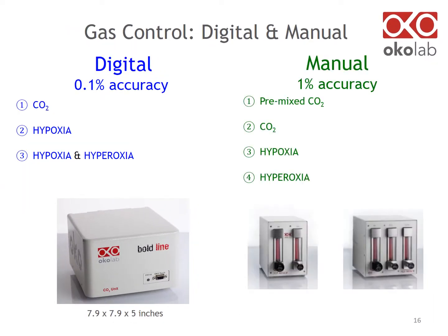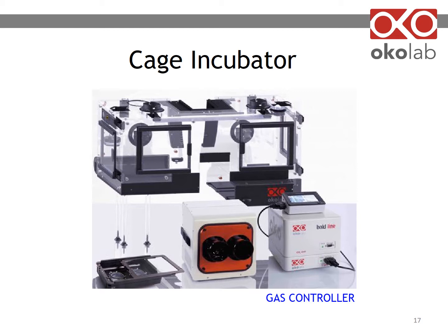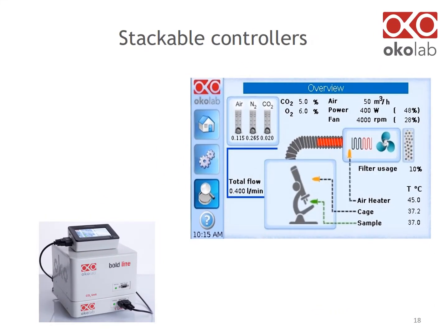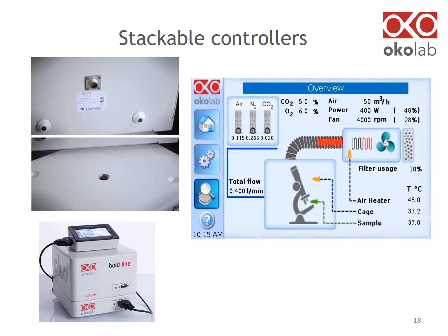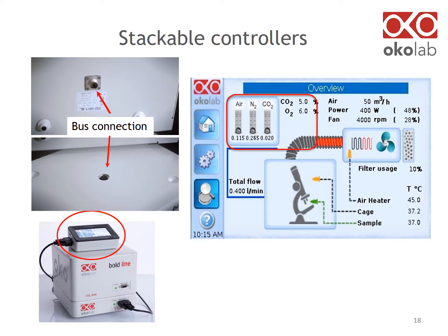We offer digital as well as manual gas mixers. Gas can be mixed to standard 5% CO2. Hypoxic or hyperoxic conditions can also be reached with the appropriate mixer. Okolab digital gas mixers offer 0.1% accuracy; manual gas mixers have 1% accuracy. You can see the stackable digital gas mixer in the blue box. Digital gas controllers are integrated through cable-less connections — simply stack the controllers on top of each other and the bus connection is established. A single touchscreen interface is used for a stack of controllers, showing data about gas concentration and flow.